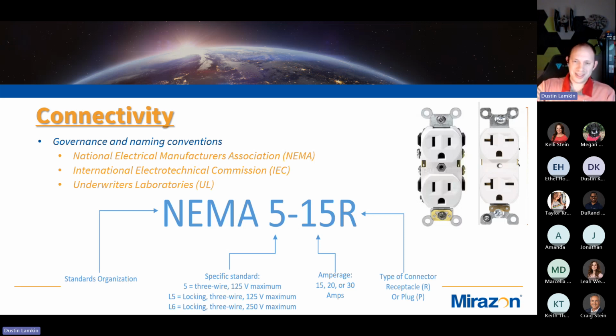So when you're looking at these, they will have your different ratings on them, and you'll be able to see what they're allowed to pull. For example, we have a NEMA 5-15R, and this one on the right is a 5-20R. The 5 here stands for the maximum voltage, 5 being 125 volts. If it was a NEMA 6, it would be 250 volts. And if it puts an L in front of it, it'll be the locking version.